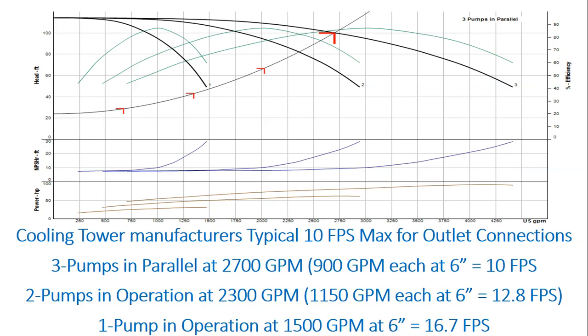Talk about sustainable engineering. That pump operating that far off its curve is going to have an imbalance on the shaft because your velocity is high. So you're going to be replacing bearings and seals. And you know, most manufacturers don't make money on their equipment today. They make it on the spare parts. So by oversizing pumps, Mr. Engineer, you are saying, thank you, Mr. Pump Manufacturer, I can actually make some money on my equipment.